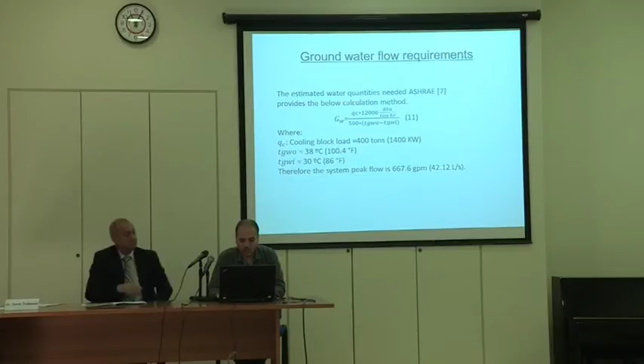Also, we checked the distance between the injection well and the pumping well, and we needed a distance of around 60 meters between the production well and the injection well, to make sure that we don't have recirculation of the heat within the aquifer. We checked with the authorities that may give us the right to use that aquifer, and they denied that right. They did not accept that we use that system; they fear that we will pollute the aquifer.